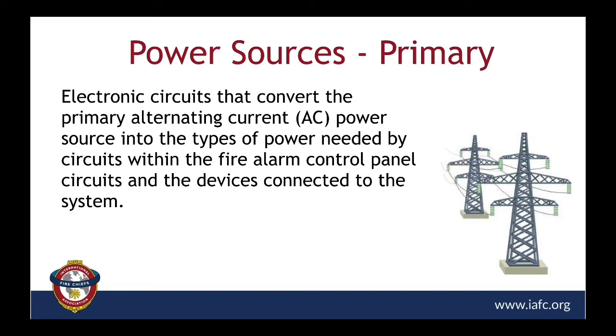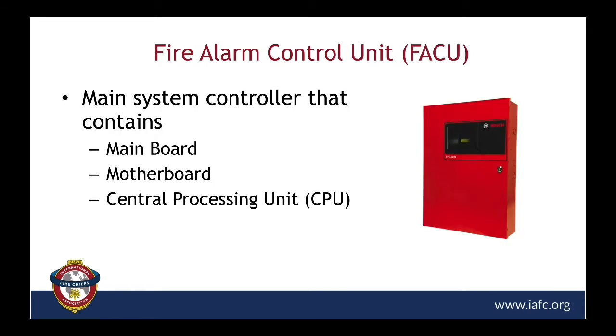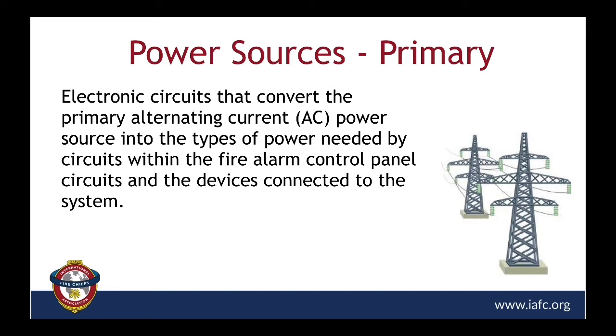Next slide. Richard, while we're on that topic about the fire alarm control unit, for a company officer, can you just speak as to what we should expect? We see a lock there, but as far as accessing the fire alarm control unit, there shouldn't be any problems getting into it, touching it, operating any of the controls. Is there any risk there to us or any danger of messing something up? Obviously, you want to have a basic understanding of the operation of a fire alarm system and the displays, which I think we will get to in other segments. There is a silence button, an acknowledge button, and we will get into all of that, but I think it's difficult to mess something up. But obviously, you also need a key to get into the fire alarm control unit cabinet, and that's to prevent unwanted people from getting in there and messing around with it. Great, thank you for clarifying that. Sure.